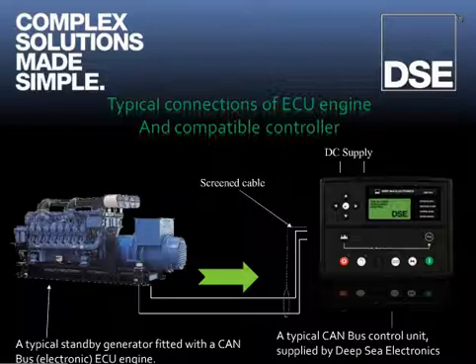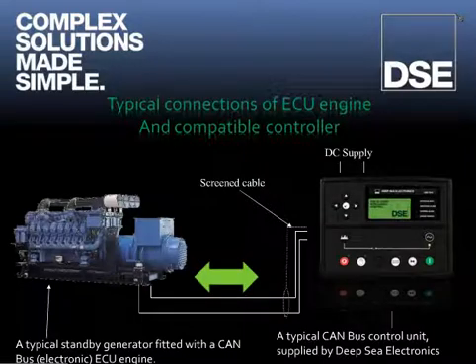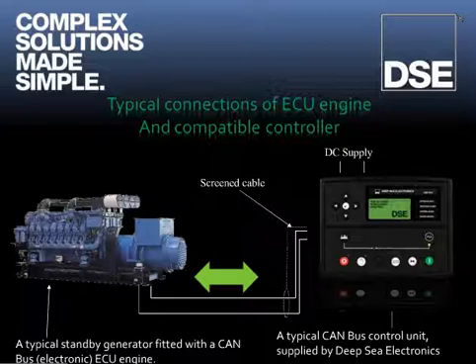Many engine ECUs also support two-way communications, allowing the DSE module to start and stop the engine using CAN messages. Engine speed control over CAN is also possible without the need for additional wiring. This all simplifies the building of a generator set and eases diagnostics should a problem occur with the engine.